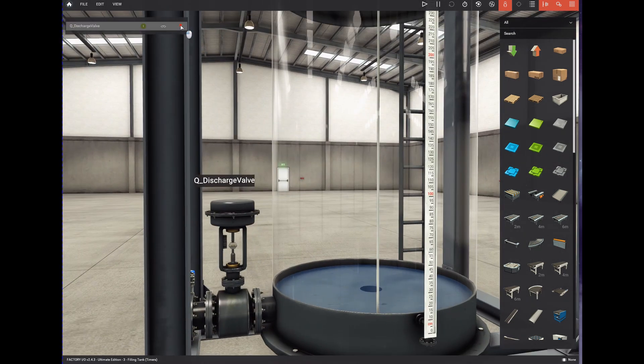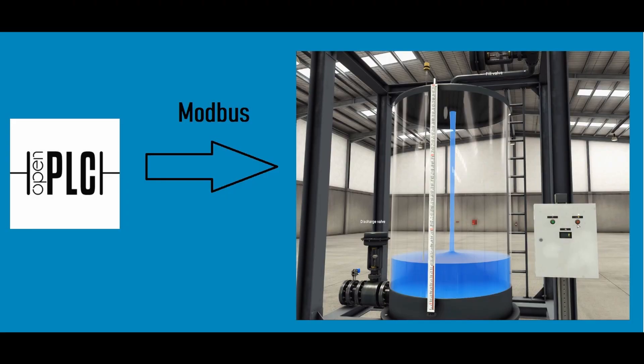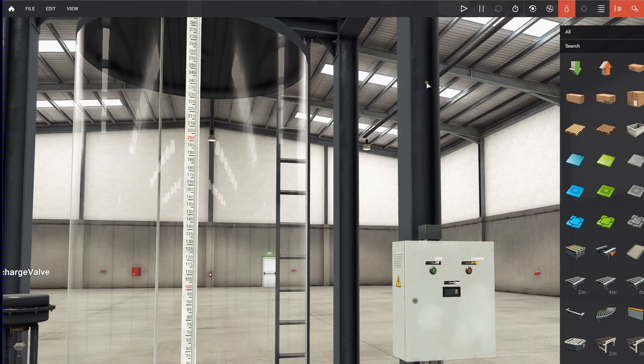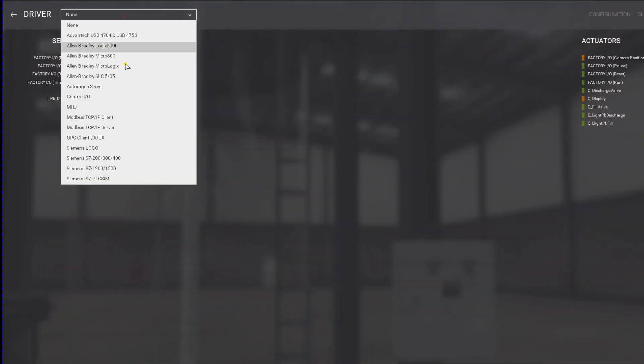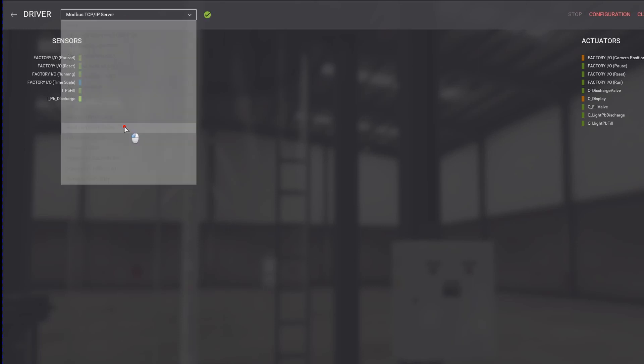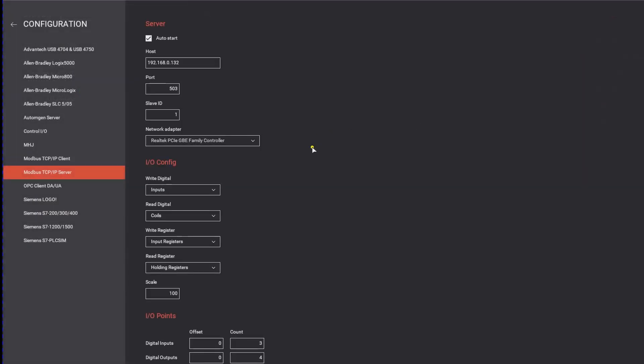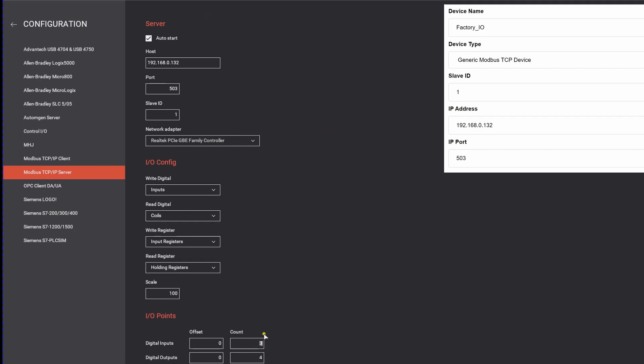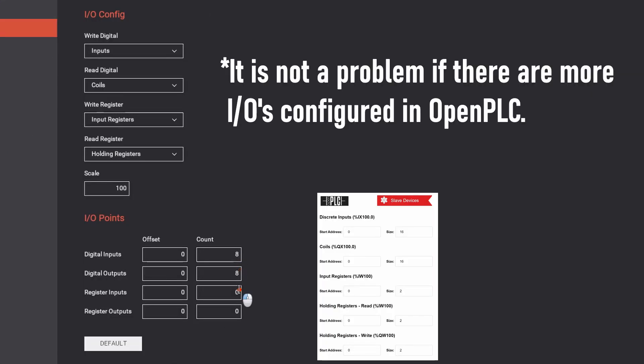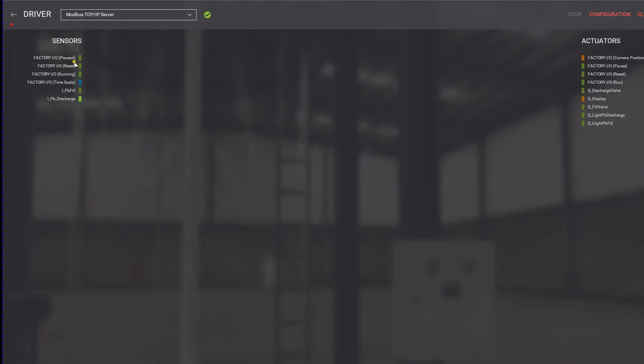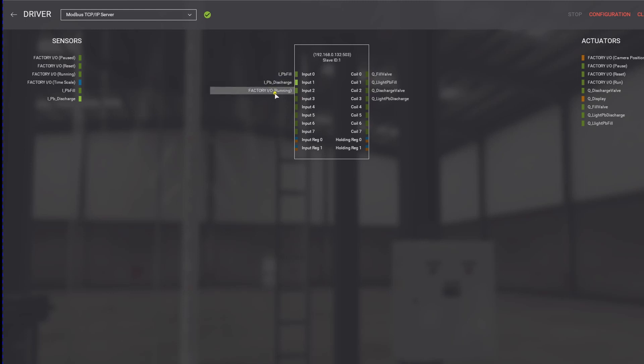The communication between the two is with the Modbus protocol. To set the communication up, you have to choose the driver by pressing the F4 key, and in the drop-down menu we are going to select Modbus TCP/IP server. We make sure the IP address is the same as we set up in Open PLC in the previous video. We set the digital inputs to 8 and also select 8 for the number of digital outputs. For the register inputs and outputs, we will set it to 2.